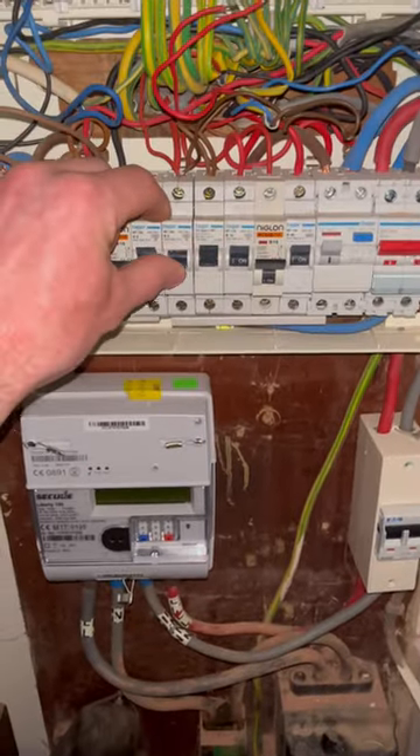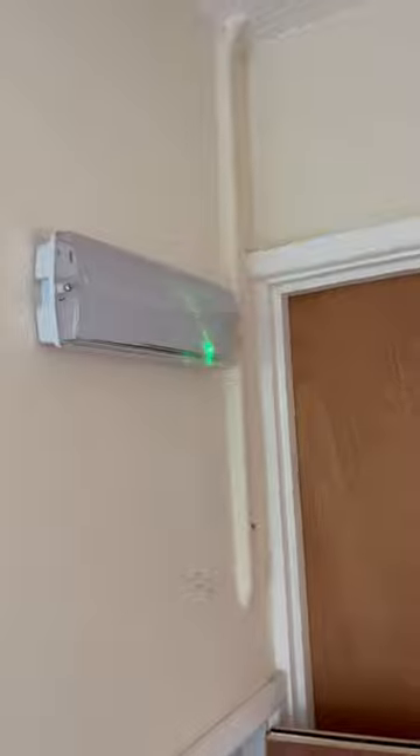Now there were four wires in this circuit breaker, which is always nice. Two were good and two were faulty. You connect your good legs back in, walk around the house, and you need to know exactly what is working and what is not working. The emergency lights came on, the smoke detectors came on, and the dining room light came on.